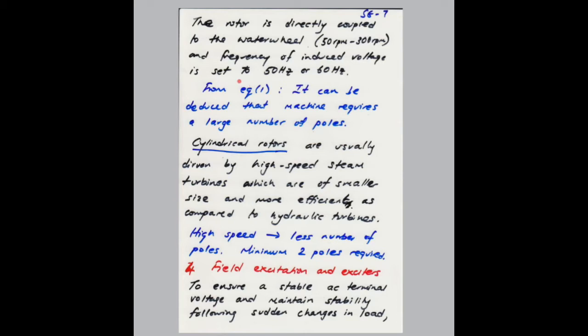So obviously, if you use equation 1, you can see that these machines require a much larger number of poles as compared to the second type, which is cylindrical rotors. So cylindrical rotor machines are driven by high-speed steam turbines. So they are smaller in size and more efficient as compared to hydraulic turbines. Because they have high speed, from equation 1 you will require fewer poles on the machine. And obviously you need a minimum of 2 poles because you need a north and a south to produce your magnetic field. And that will be the lowest number of poles that you can use.